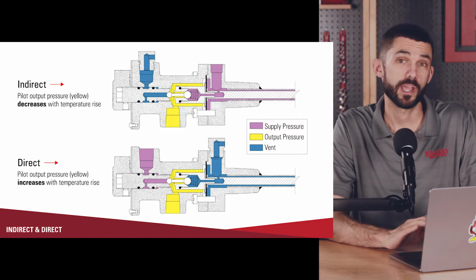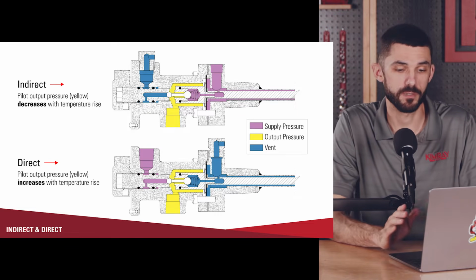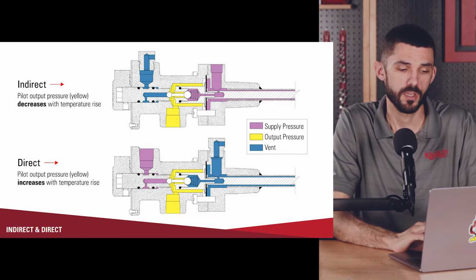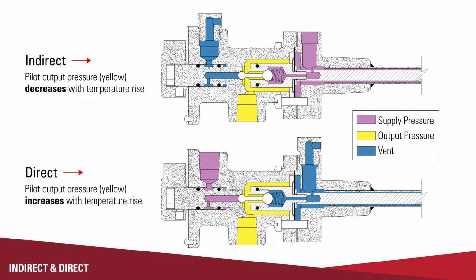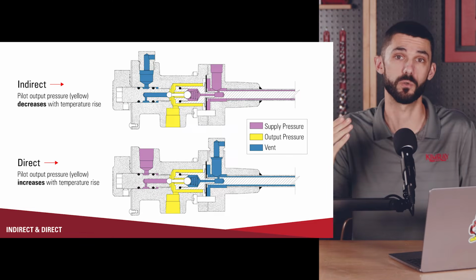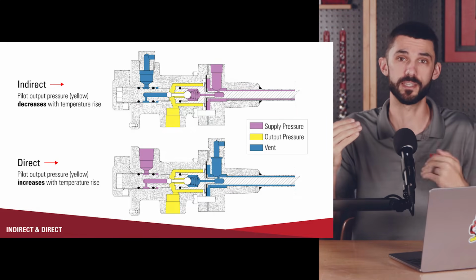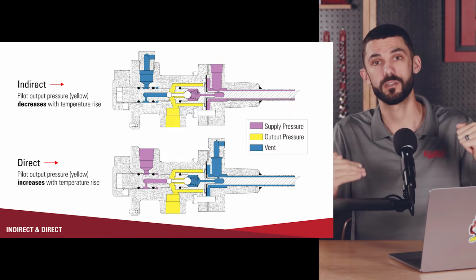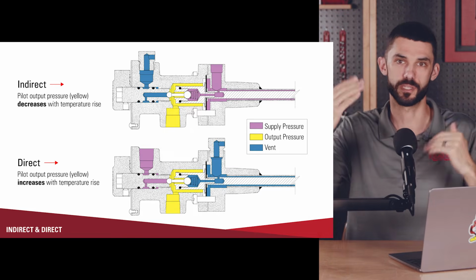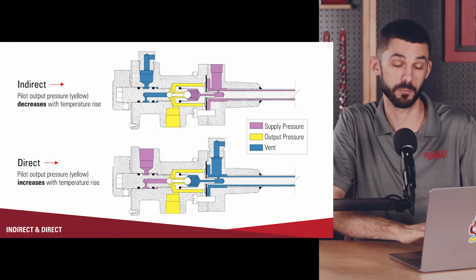Our temperature controllers can be direct acting or indirect acting. They can be switched from one to the other without adding any additional parts. You just have to put the supply and the vent in different spots. You have to switch the two. So direct acting temperature controllers, when you have a rise in temperature above your set point, the controller will have a pneumatic output. So it's a direct action. Above set point, you're going to have output from the temperature controller. In indirect mode, if you are above your temperature set point, the controller will be venting its output. And then if you go below your temperature set point, the controller will have a pneumatic output. So it's kind of an opposite reaction from the process temperature and what's happening with the process temperature.